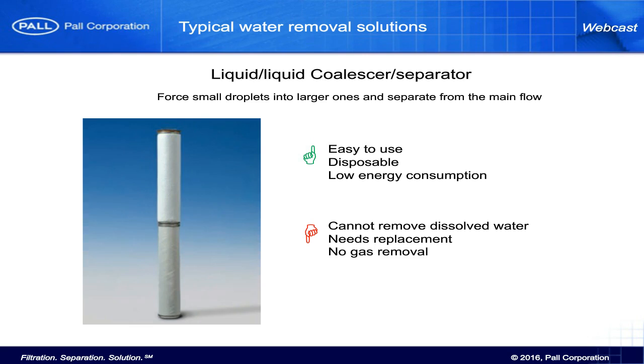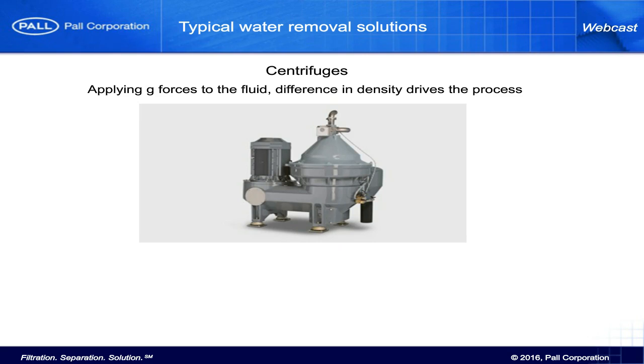One of the most common methods to remove water from oil is to use a centrifuge. Its concept depends on the difference in density between water and oil. So when you think of a sample that you leave alone on a table, gravity will act differently on water than it will on the oil. That is why, naturally, the water will drop at the bottom of the oil sample.